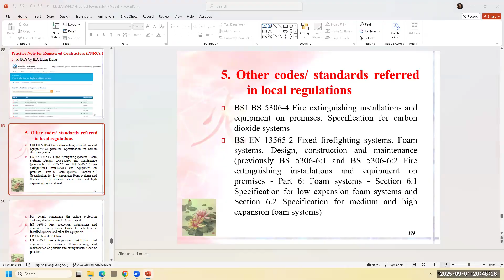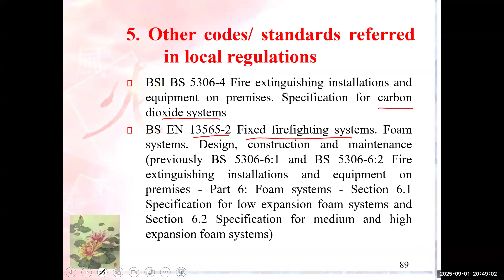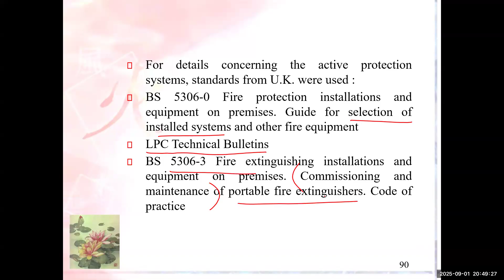For example, we have the British Standards, such as 5306 Part 4, which is related to fire extinguishing installation and equipment on premises, mainly for carbon dioxide systems. Firefighting system 13565 Part 2 is for foam - related to foam - but we also have a guide for selection of the installations, the Loss Prevention Council Technical Bulletin, fire extinguishing installation with commissioning and maintenance of portable extinguishers. So these are some codes and standards related to fire local regulations.